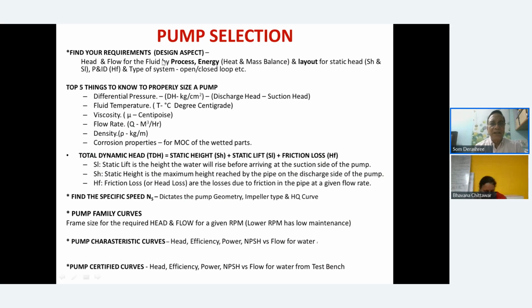So once you have arrived at the design figures, there are top 5 things to know properly to size a pump. One is the differential pressure. What is the differential pressure from suction to discharge that it has to develop? What is the fluid temperature in degrees centigrade? What is the viscosity? You may have centipoise or you may have Pascal seconds. Flow rate, what is it in meter cube per hour? What is the density? And what are the corrosion properties, to decide on the MOC, material of construction of the wetted parts of the pump, basically.